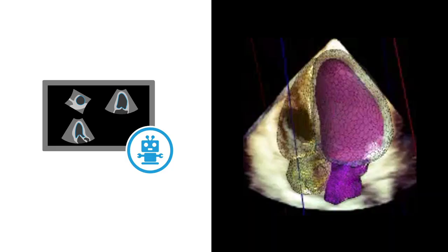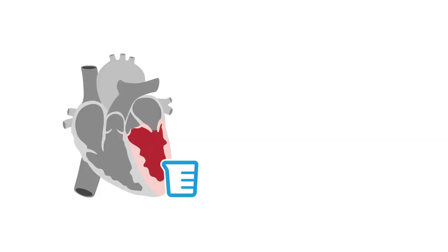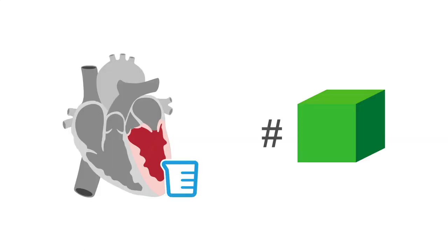The software then automatically detects the whole endocardial surface. Once confirmed by the operator, a 3D cast of the left ventricle is developed. The volume is then measured by counting the voxels contained within the left ventricular cast.